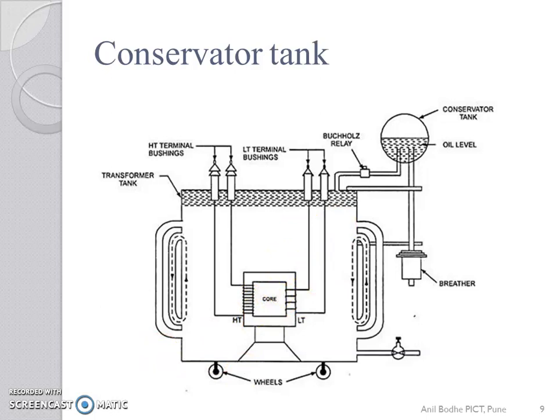When the transformer becomes warm, oil expands and the air at the top of the oil is expelled through the breather. When the transformer cools, oil contracts and the outside air is drawn into the transformer through the same path. This process is called the breathing of transformer. Meaning, in and out of air in the conservator tank is known as breathing of transformer.